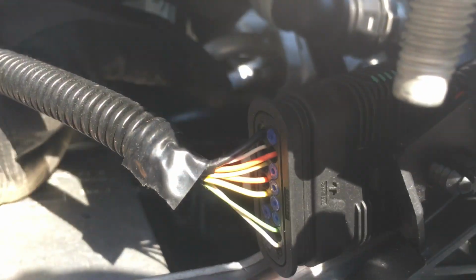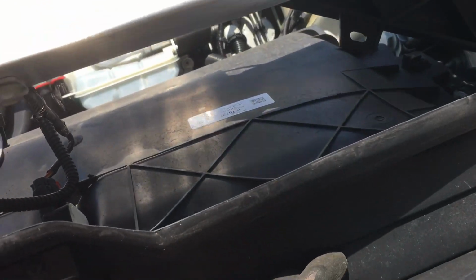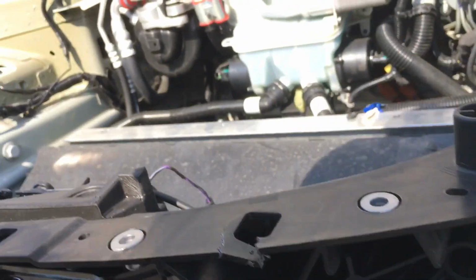So here's, what heat exchanger is this? Okay, so there's a condenser right here. So here's your hot gas discharge. Here's your liquid line return down there in your condenser. And the condenser, the airflow is controlled by these flaps, so you don't get airflow over your condenser all the time. And it looks like they also have glycol back there, so they got part of their glycol system.